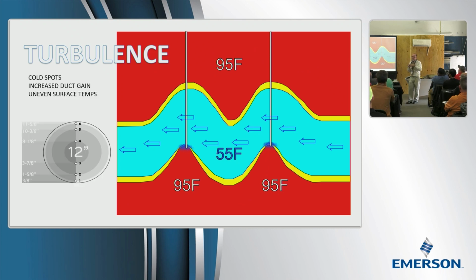Turbulence is also a problem because this is about that mass flow rate. We were talking about mass flow rate this morning with regard to removing molecules with a vacuum pump. Now we're talking about trying to put those pounds of air down the middle of the duct. And we know from, any of you guys do duct traverses, okay? Most of the air is moving down the middle, right? That's why we measure it that way, and so we take more readings away from that. I believe generally if you take a velocity pressure reading in the center of a straight duct and multiply times 0.9, that's pretty close to what it's going to be. So most of the air wants to go down the middle until we start putting offsets and turning it.